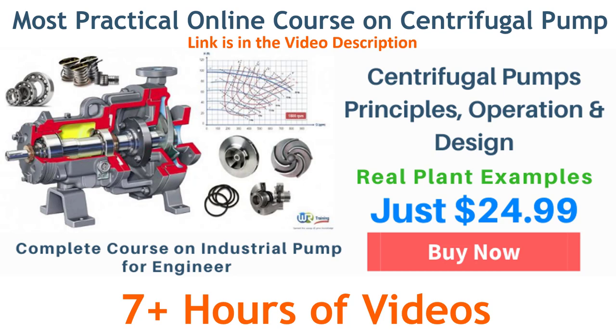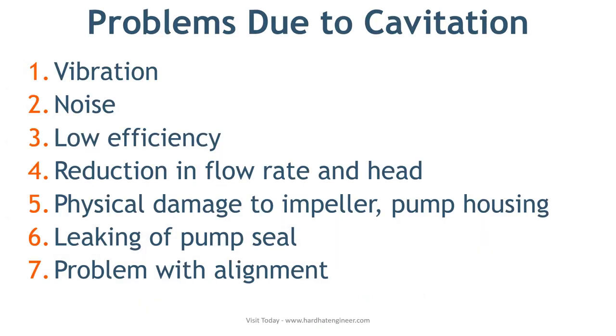Some of the potential problems that come with prolonged cavitation in the pump include: vibration, noise, low efficiency, reduction in flow rate and head, physical damage to the impeller and pump housing, leakage of the pump seal, and problems with alignment.